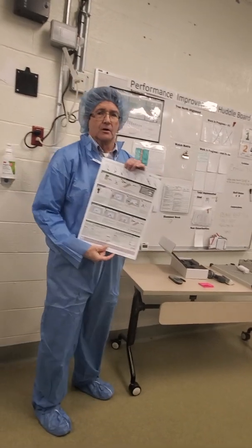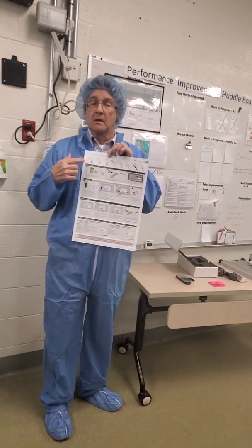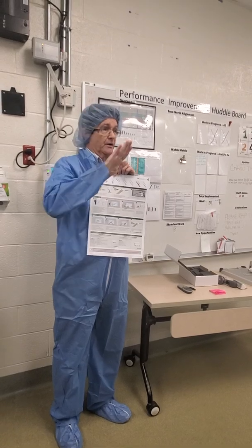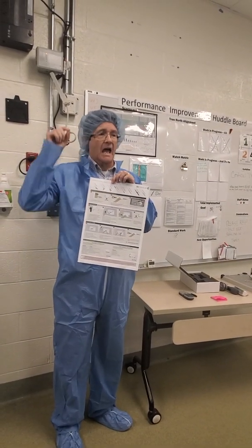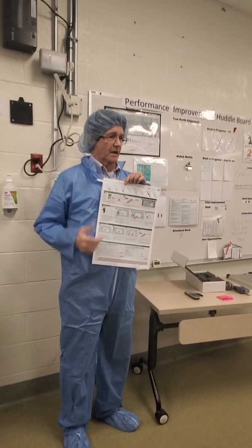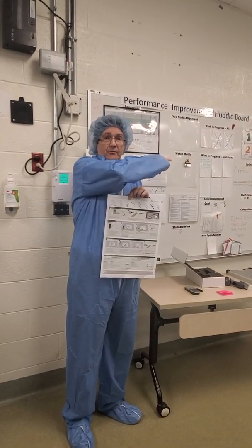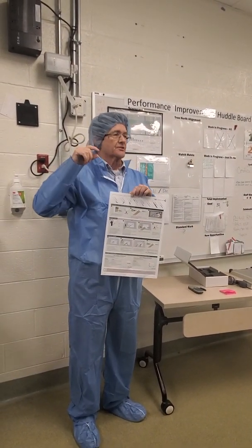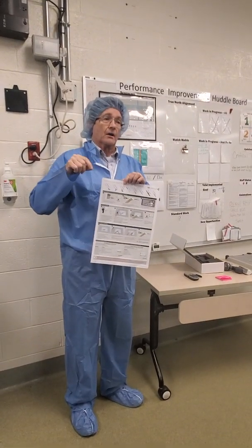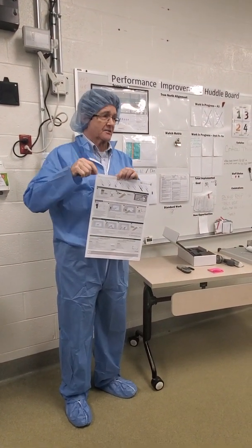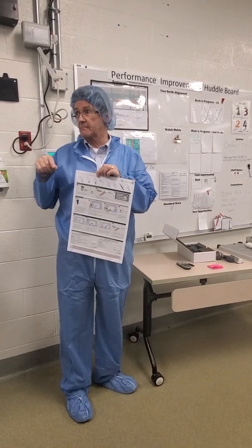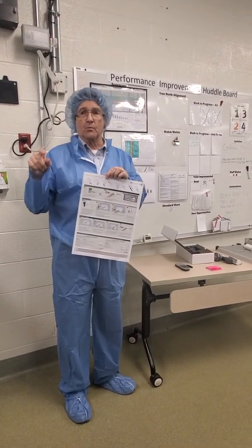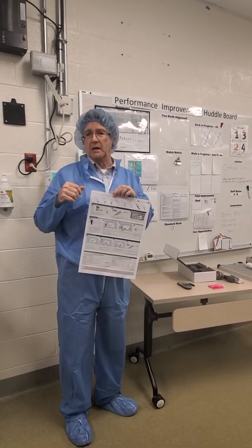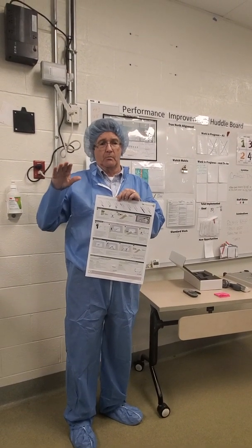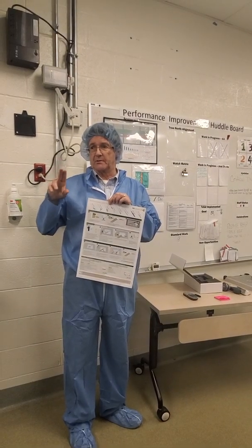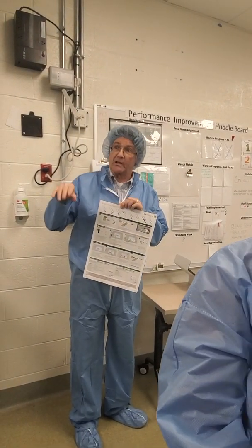Right here is a chart for critical probes. The surgical probes that you got, they're critical. They get leak tested every time. Okay? That other probe there for the implants, that's called semi-critical. That only needs to be tested at least once every 3 months. You can test it once a week. You can test it after every use, whatever you wish, but no less frequent than once every 3 months. More frequent, fine.